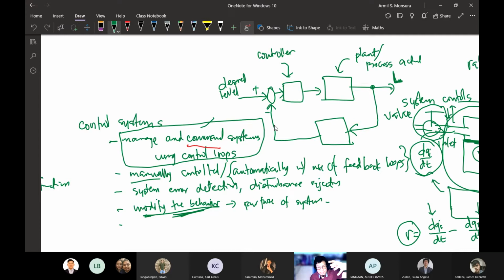Because the higher the difference, the more you want your controller to open the inlet valve and close down the outlet valve, so that the level inside the tank would rise faster. Then if it is now close to that level, your controller would be able to detect that, because the difference is very small, so the controller would try to lessen the input from the inlet.